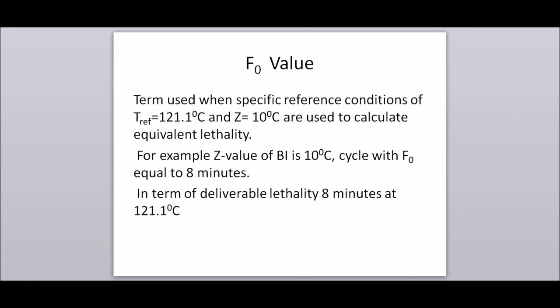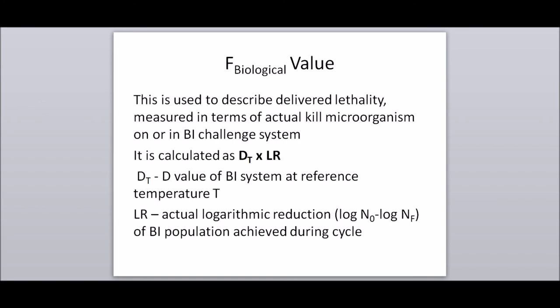F zero value: the term used when a specific reference condition of T-reference equal to 121.1°C and Z equal to 10°C are used to calculate equivalent lethality. For example, if the Z value of a BI is 10°C, a cycle with F zero equal to 8 minutes delivers lethality equivalent to 8 minutes at 121.1°C. F biological value: used to describe delivered lethality measured in terms of actual killed microorganisms on or in a biological indicator challenge system.